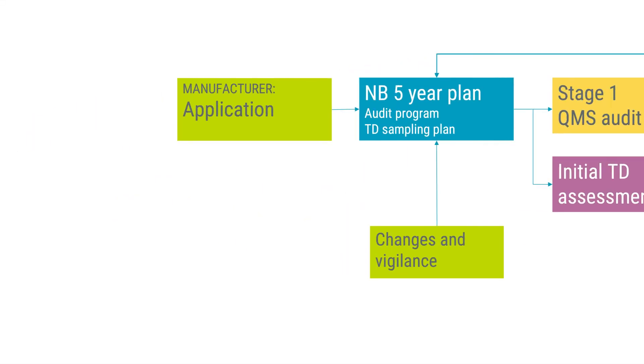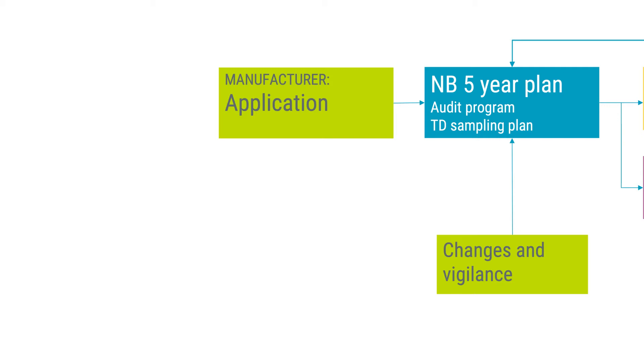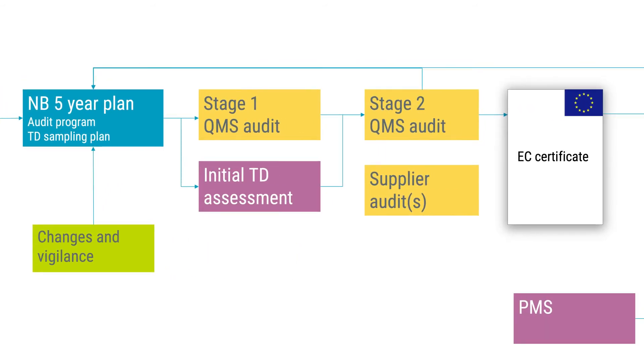The start of the initial conformity assessment is the manufacturer's application to the notified body. Based on the application data, the notified body should be able to set up a so-called 5-year plan that shall cover all planned activities for the coming certification cycle. The 5-year plan then needs to be continuously updated during the cycle. By default, initial certification requires a QMS on-site audit and an initial technical documentation assessment.